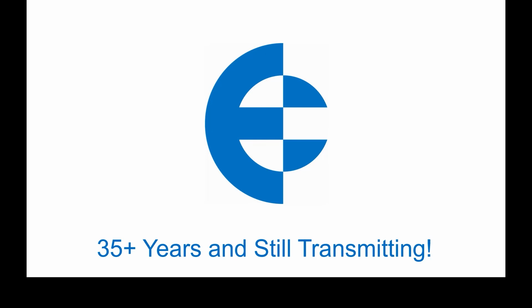Well, if we use a repeater and we are transmitting serial data, then the bandwidth will drop in half with each repeater that we add. However, if we are just transmitting 4 to 20 milliamp and discrete signals, the actual amount of I/O is literally negligible. For example, a 4 to 20 milliamp signal, 16-bit register, that's only 2 bytes of data. So if we're just transmitting 4 to 20 and discrete signals, as well as some SDI sensor data, there isn't a specified limit on the number of repeaters. But I would say after you get to about 5 or 6 repeaters, you might want to give us a call and just run through the application and make sure we're not pushing things beyond the limits.